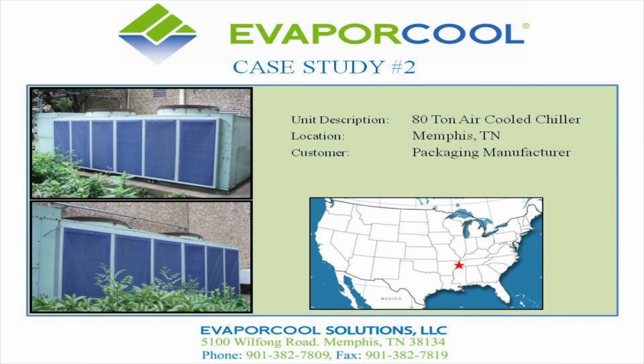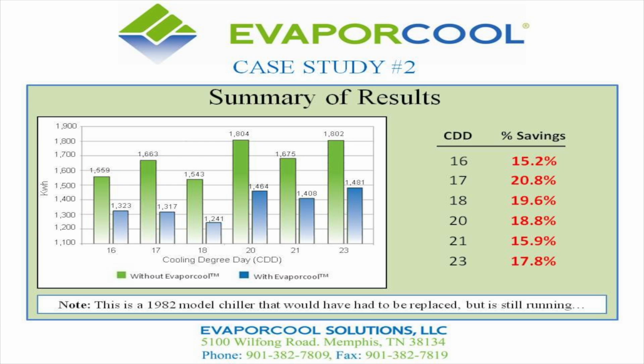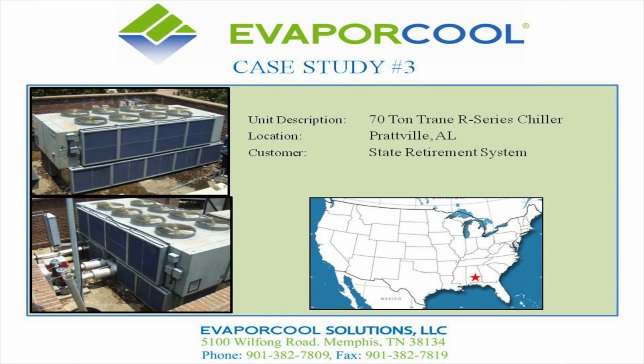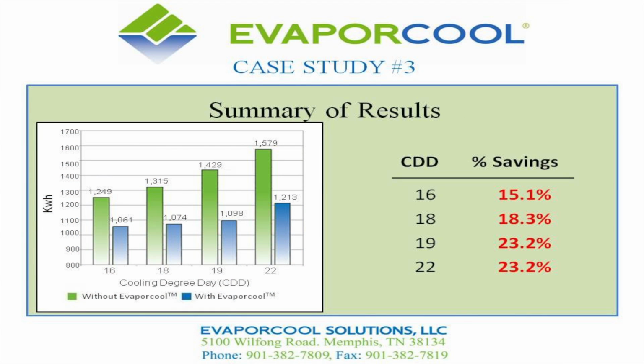An 80-ton unit in Memphis, again, you can see the before and after, with 15%, 18%, 19% savings. A 70-ton unit in Alabama, again, same savings, averaging around 20%. We'll talk a little bit about this, and I'll have Jack talk more about what's happening on the maintenance side, but there are additional maintenance savings that occur.